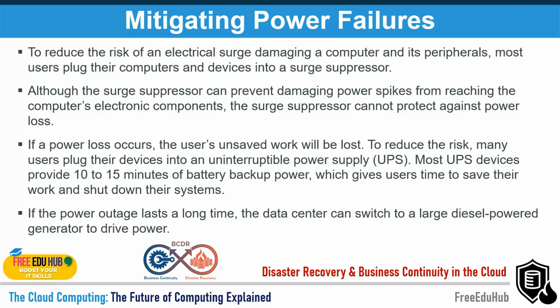There is a mathematical calculation for this, based on how much power is required by your data center, and whether the UPS is powerful enough to power up those systems for 15, 20, 30, 45 minutes or an hour. That really depends on the storage capacity of power in your batteries.